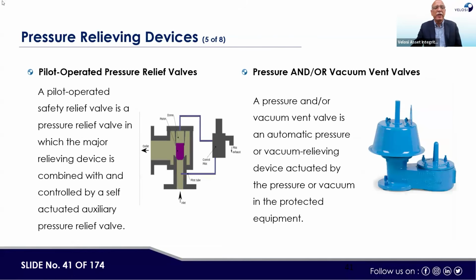Then here, pilot operated pressure relief valve, this is the pilot. And here if you see the pilot tube and another tube from there, as the differential pressure crosses, then this pilot will help this disc to move up and fluid will go out here.